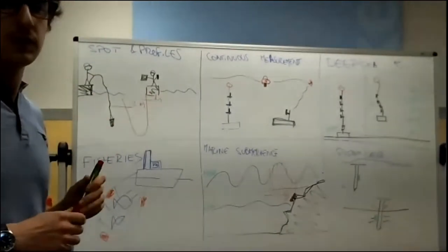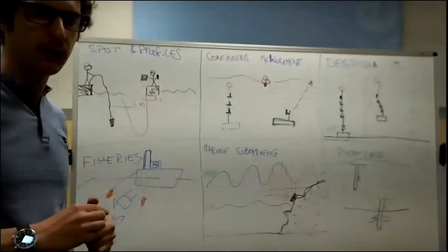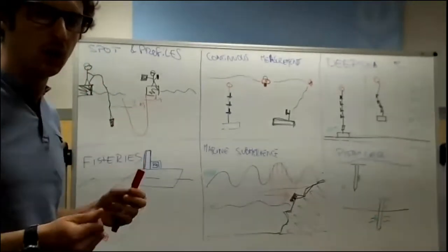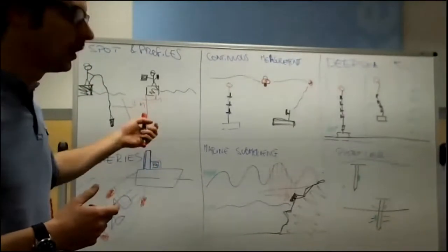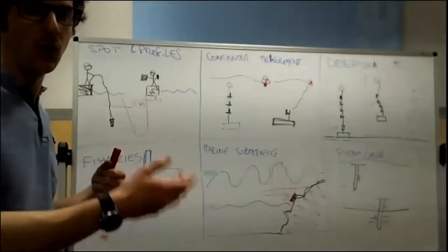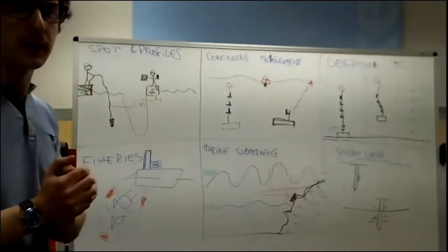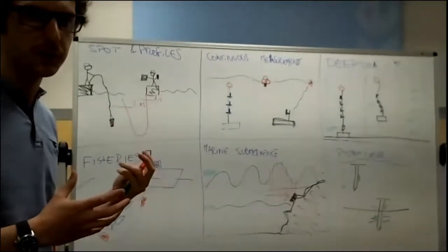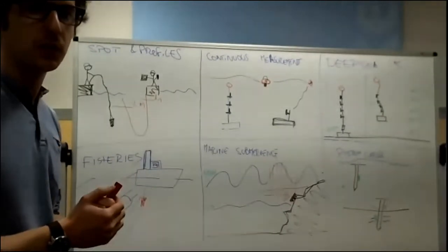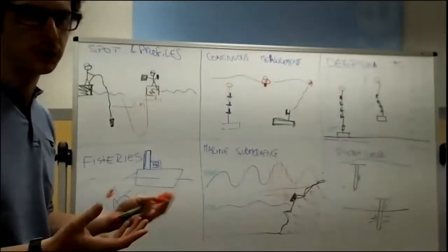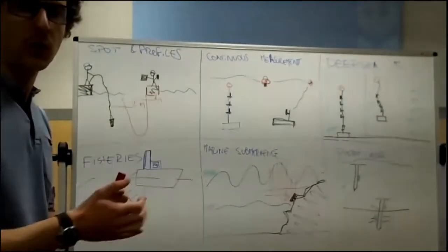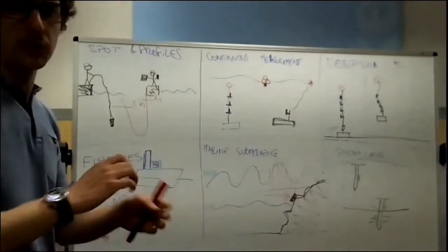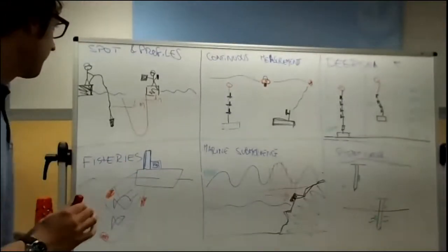And the interesting thing on this is that the Ysense is keeping all the information of this schedule, so you can repeat the operation all the time until you manipulate it. This means that you can even pre-program the Ysense before the deployment and leave the instrument to any operator. The only thing you have to tell this person is put it in the water, wait, deploy, recover, and that's it.